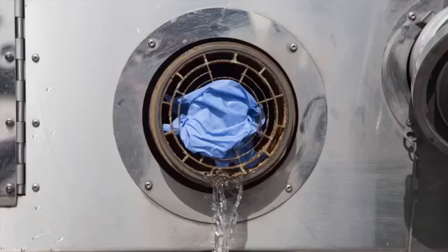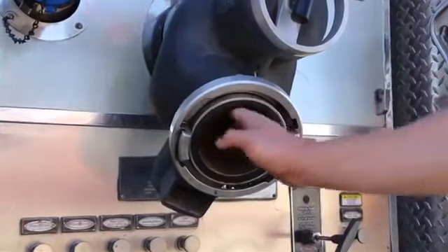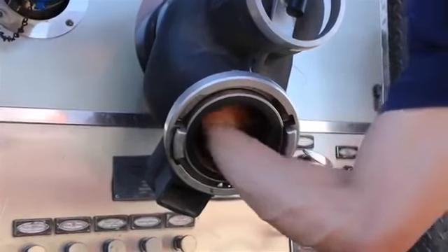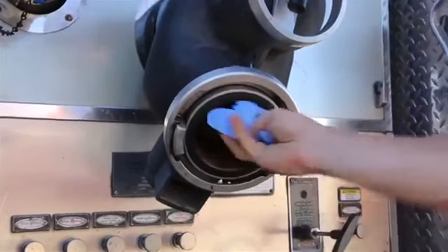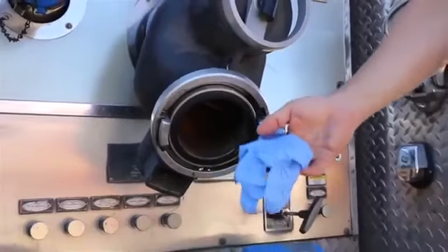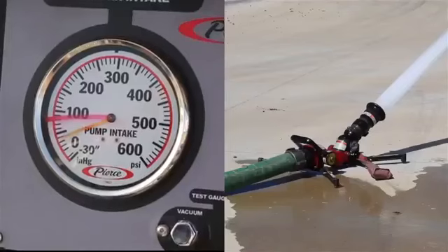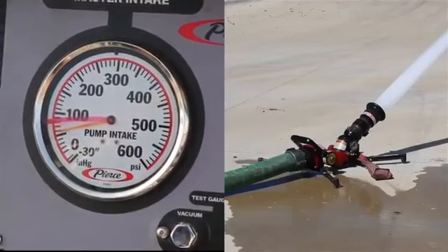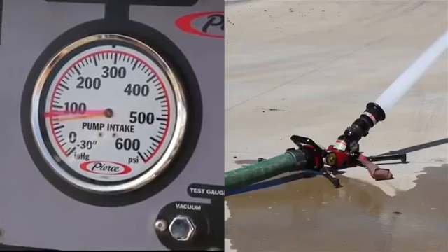Another supply problem that will present in the same manner is debris in our intake strainer. The fix for this issue is not quite as straightforward. In this case, we have to shut down the supply and either remove the obstruction or move the supply to another intake. Once we have mitigated these problems, we will observe a more accurate residual pressure.